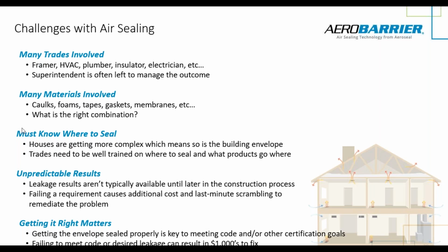The other two are unpredictable results, and getting it right matters. Most tests today are done at the end of construction. So knowing that you're going to pass a blower door test, or meet the requirements, or even just meet the expectations or the spec that was set so that the mechanical system operates effectively, can be a challenge because the results aren't known until the end. And really getting it right matters.